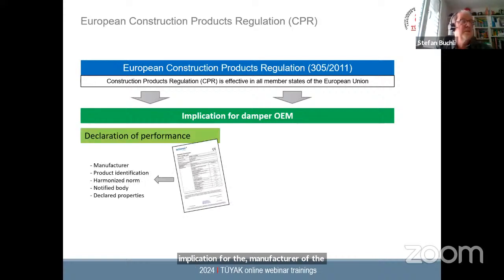They have, on one side, the obligation to issue the so-called declaration of performance for their products. So if they deliver a fire damper, as an example, this paper is mandatory and goes with the fire damper. That means in this paper you see all the detailed information. You see who was the manufacturer of this fire damper. You see a clear product identification. You see the relevant standards which these components are conform with. Then you see the notified body which has done the whole testing of these components. And you see also the declared properties, like, for example, with which actuators this damper has been tested. So this is a very useful document, which really gives you a quick overview of what you get when you buy this component, the fire damper.